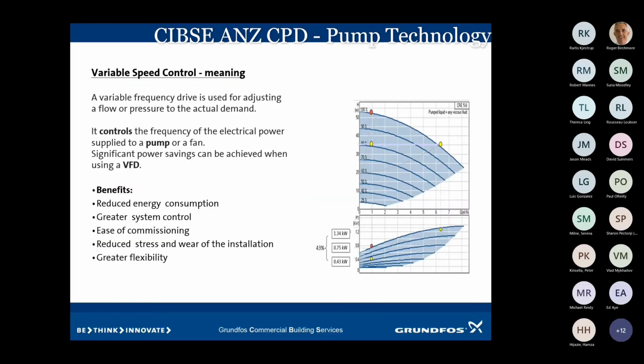And here you can see this is a multi-stage pump. Has a nice steep curve, but no different concept to the variable speed. Now we have multiple curves. The fixed speed pump would be the 100% pump curve. The other curves are between 25 and 100%. And looking at the 2 dots, what we've got here now is a pump running at around about 6.5 cubic meters an hour, and it's producing about 35 meters head, and that would be the peak load.